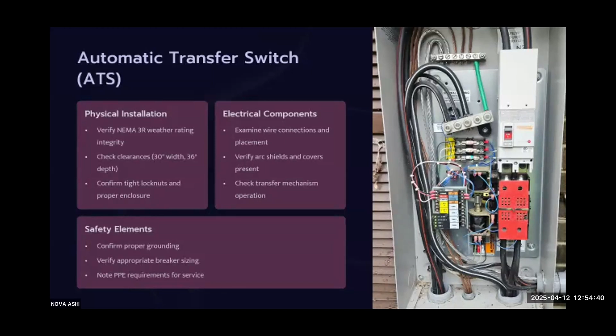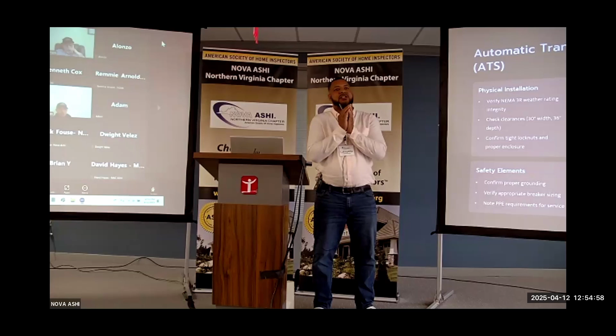Yes. Now, keep in mind, if it's an essential setup where you may have an ATS just for a certain amount of circuits, let's say the main panel is just feeding an ATS, then the main panel still stays as it is. But if it's whole house like this, then that's where it actually becomes it. It comes down to, is the ATS effectively being used as a sub panel or main?